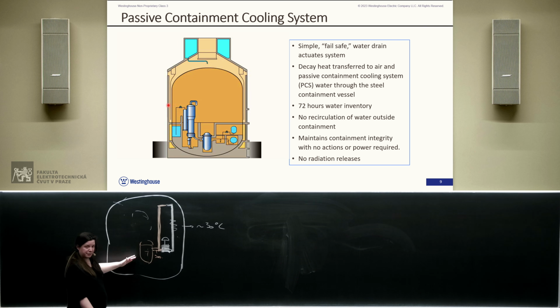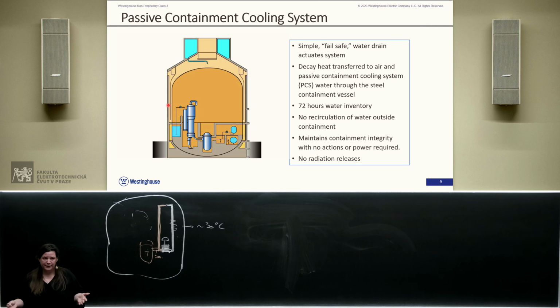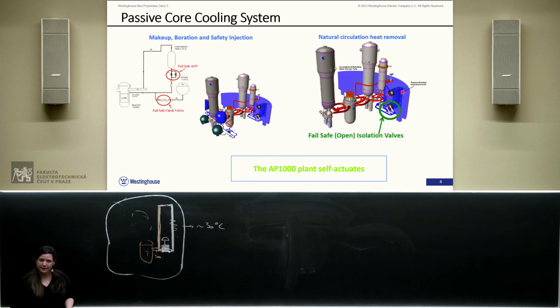Some of it may rain into our containment cell, but most of it is collected alongside the inside surface of the containment, where we have a gutter system—just like gutters on your roof—and it's brought back to our in-containment refueling water storage tank, the big tank we use as a heat sink for the heat exchanger removing heat from the core.